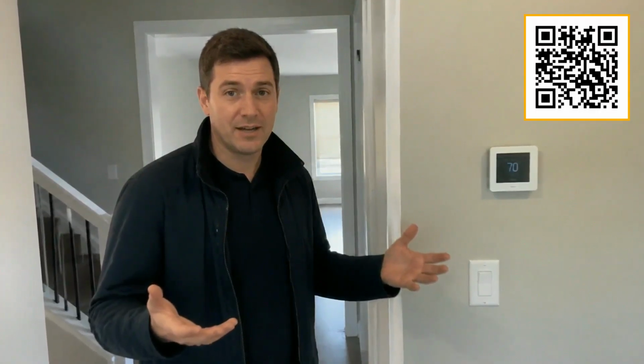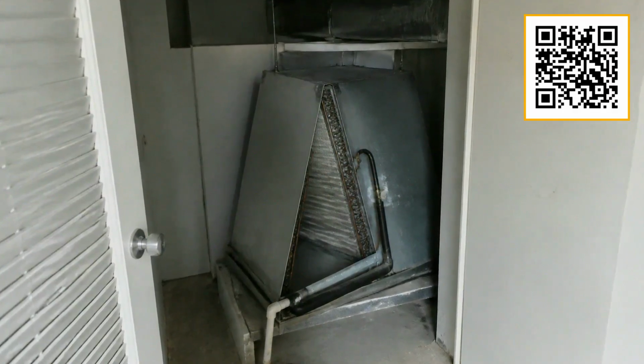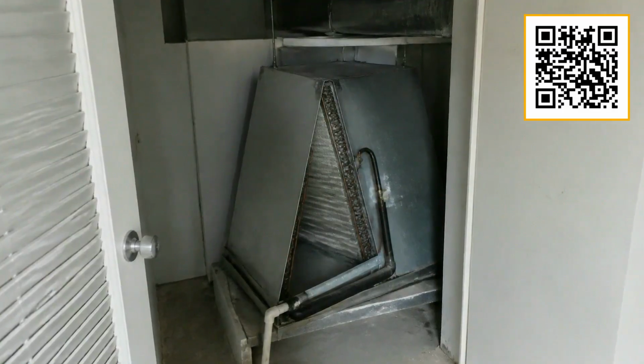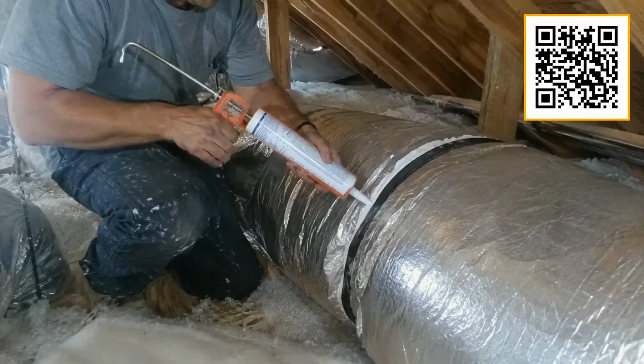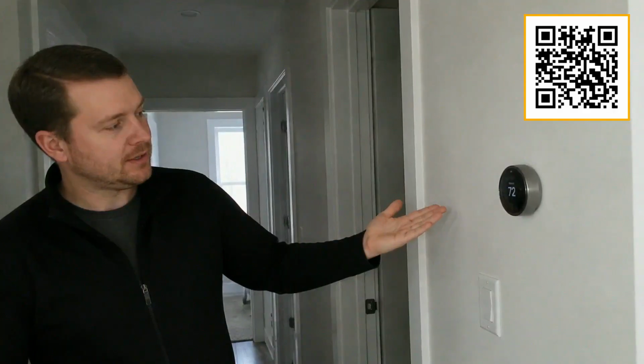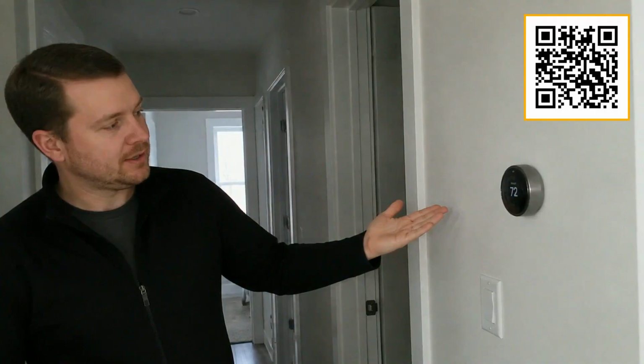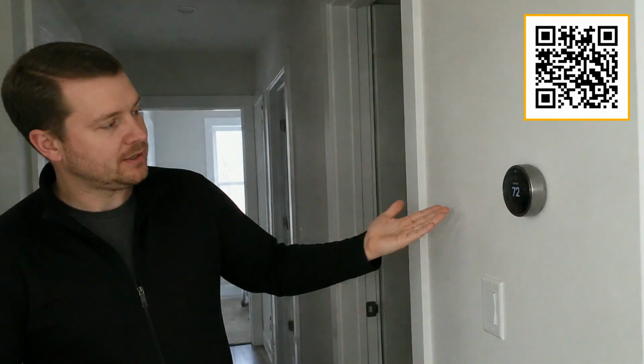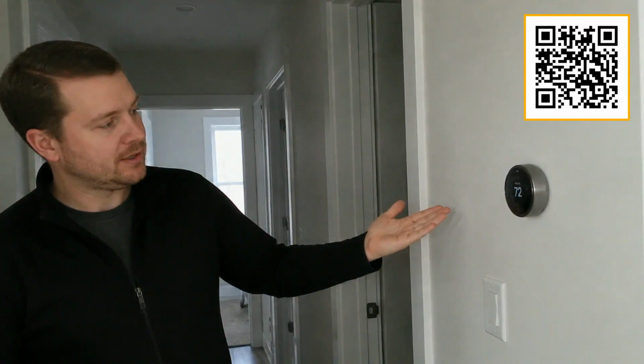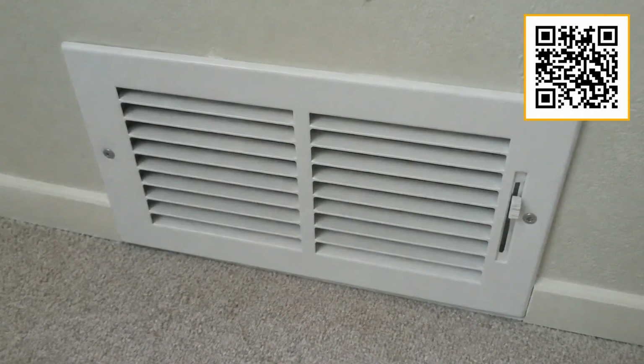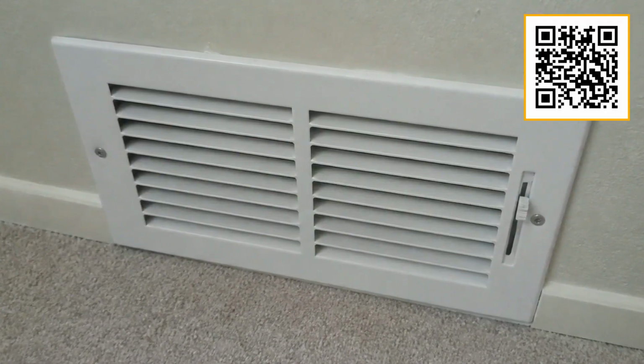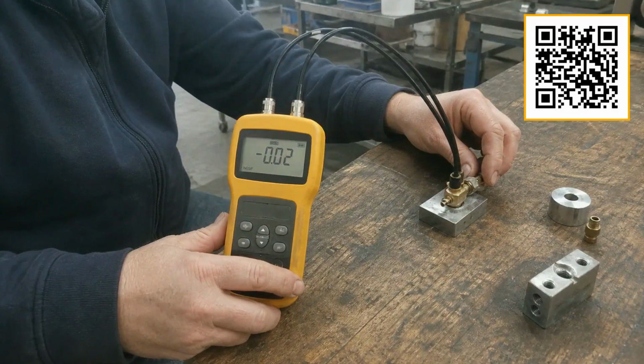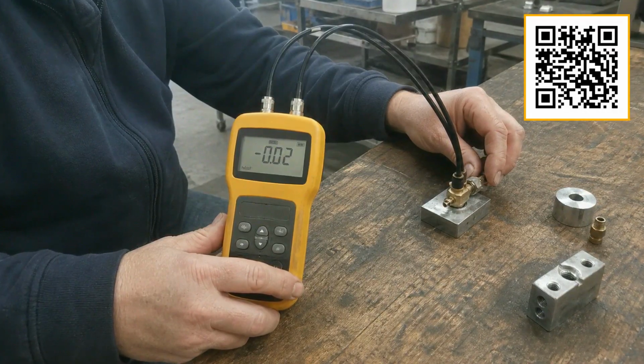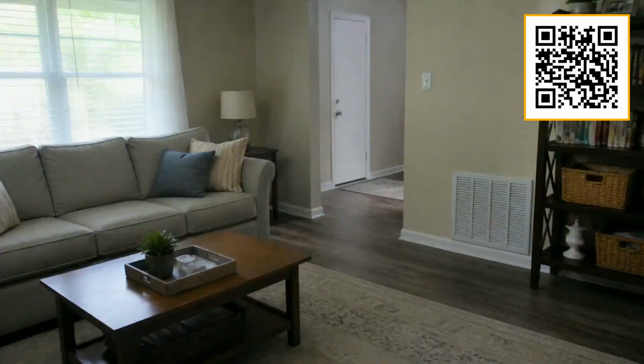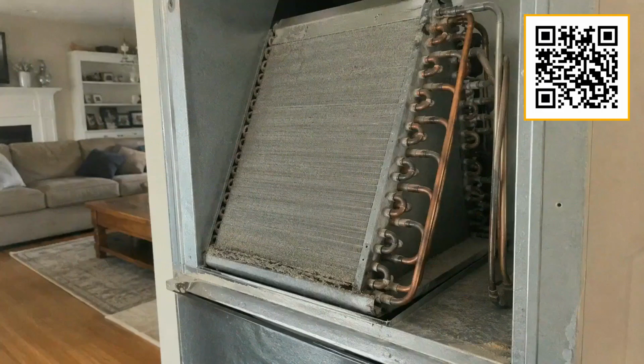The cost for a balancing visit is typically modest compared to compressor or blower motor repair. Here is the longer-term piece that I think is genuinely underrated. If you want to take real pressure off your HVAC system and reduce what it costs to run, the most durable answer is insulation and air sealing, not vent closing. A room with good insulation in the walls, ceiling, and around windows holds its temperature far longer on its own. Your HVAC system does not have to work as hard to maintain comfort throughout the house. That spare bedroom stays closer to the right temperature without the system running to keep up. That is the old, patient approach to the problem, the one that takes more effort up front, but pays you back year after year without wearing out your equipment.